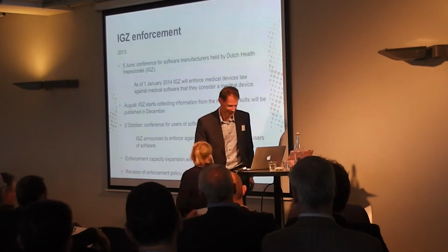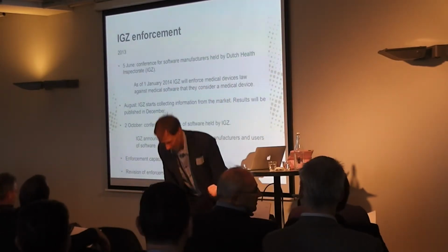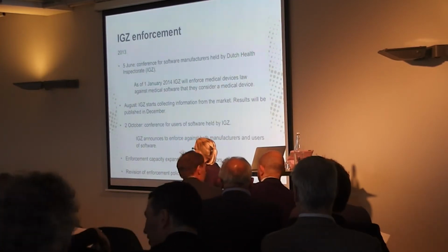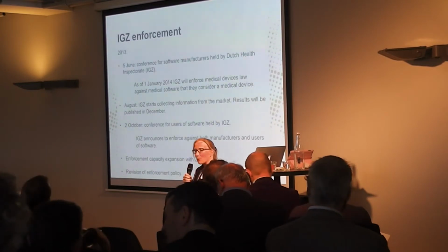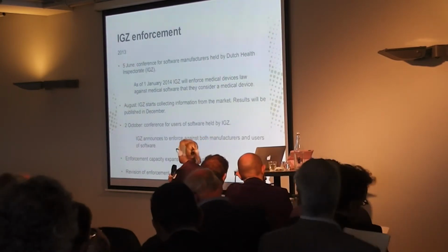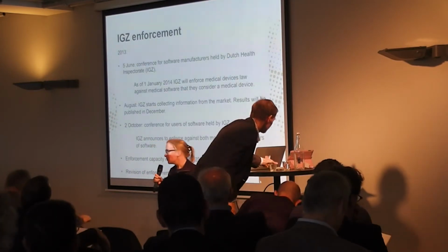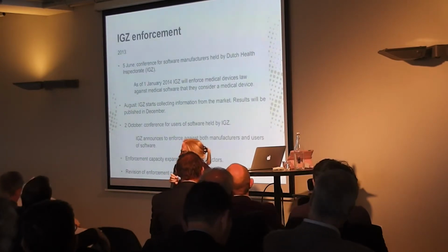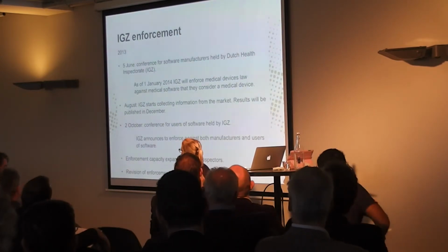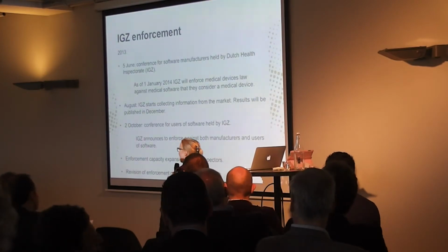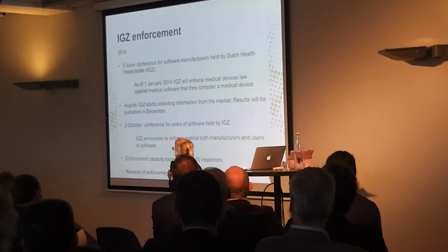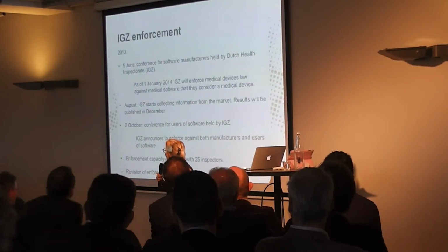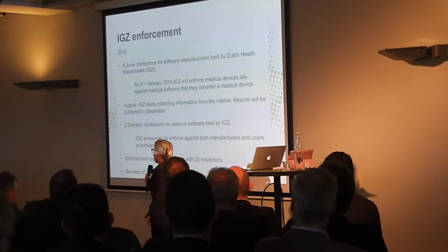Yes, thank you, Erik. So we did the correct slides. In the following four slides, I will quickly go through some recent developments in enforcement of medical devices law. If you are already working in medical software, you might have become aware that the Dutch Health Inspectorate, IGZ, is now announcing it will start enforcement as from 1 January next year. They announced that already at a conference on the 5th of June.